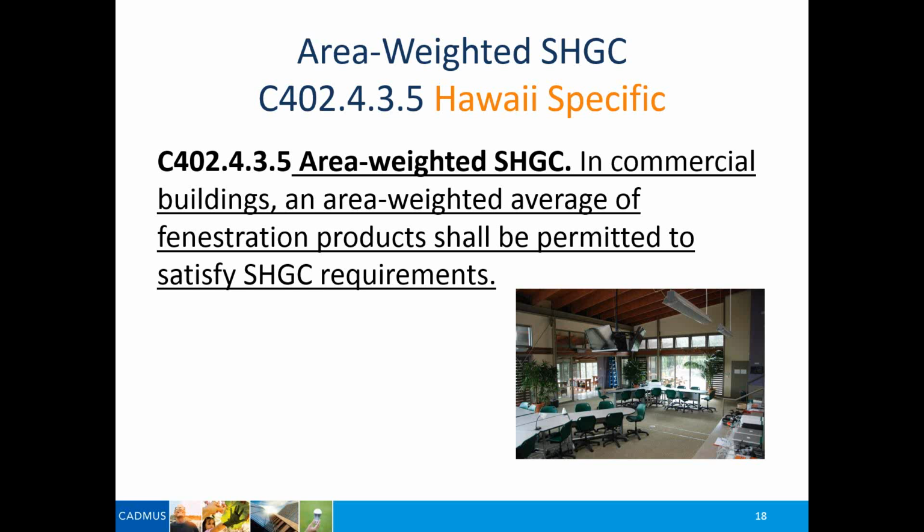Number one, and again, this is starting with single pane glass, we exempted the north face of any, in this case, residence, and now we transferred that to buildings. Why exempt? Because when you don't have direct solar light, all you have is the ambient temperature compared to the interior temperature. And in Hawaii, very often that delta T, that difference, is as little as 10 degrees, 85 outside, 75 inside. Even a single pane of glass will do a good job of shielding you from that temperature difference.